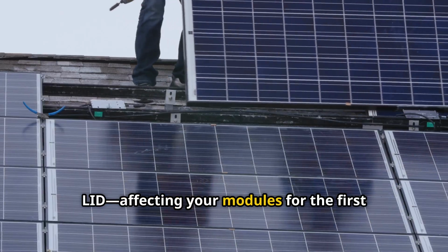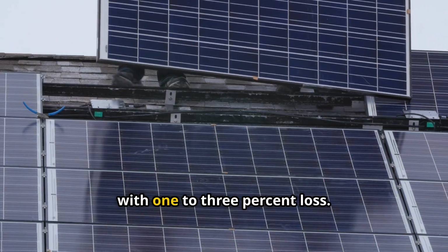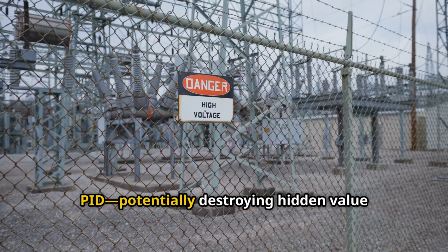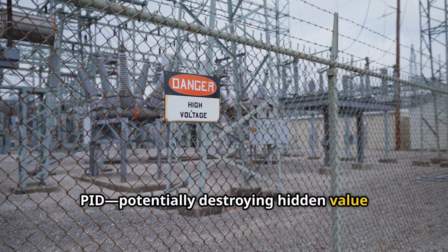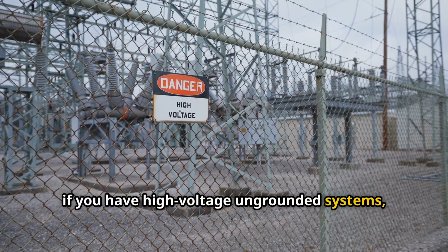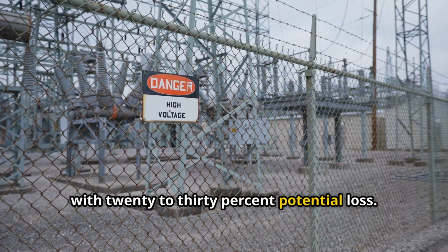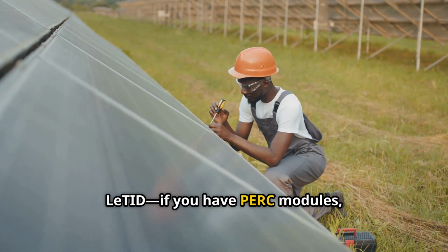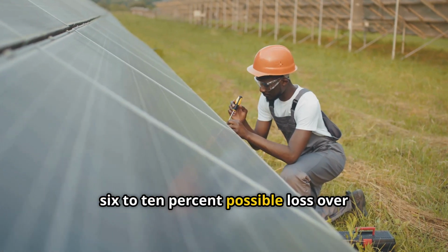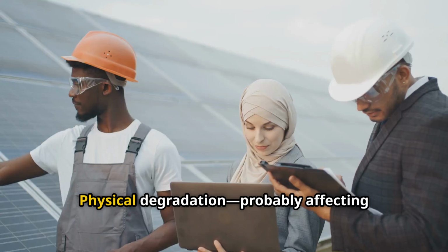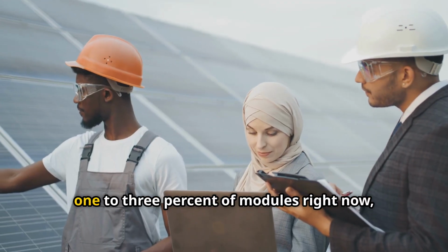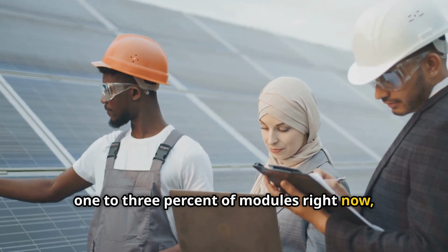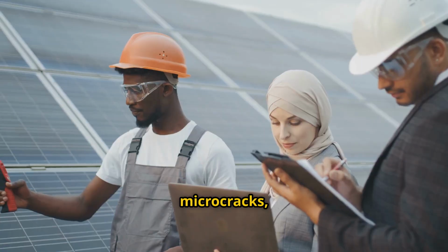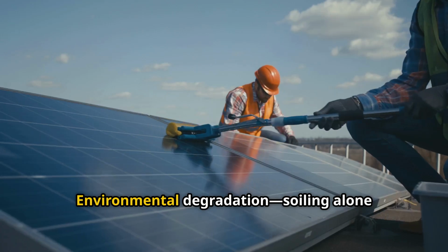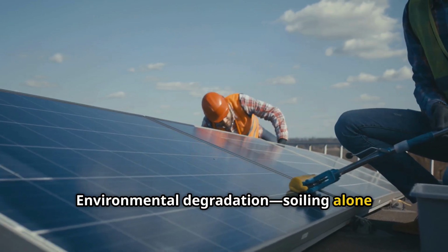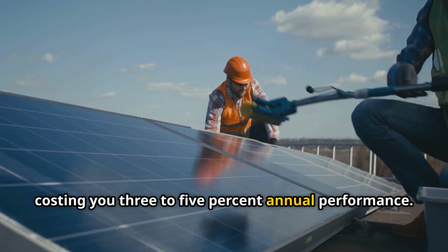LID, affecting your modules for the first 12 months with 1 to 3% loss. PID, potentially destroying hidden value if you have high voltage ungrounded systems, with 20 to 30% potential loss. LeTID, if you have PERC modules, 6 to 10% possible loss over 3 years. Physical degradation, probably affecting 1 to 3% of modules right now, with hotspots, microcracks, and diode failures. Environmental degradation, soiling alone costing you 3 to 5% annual performance.